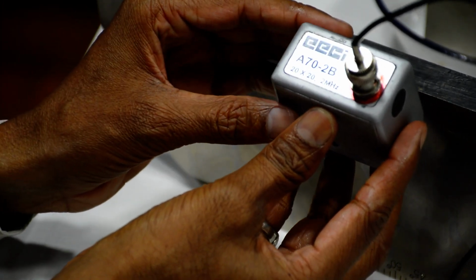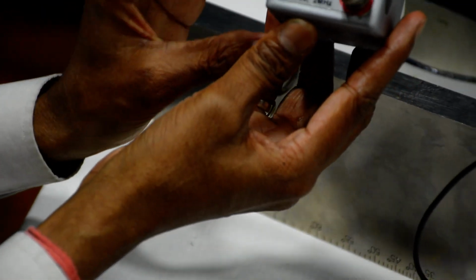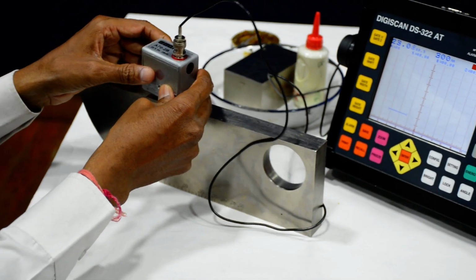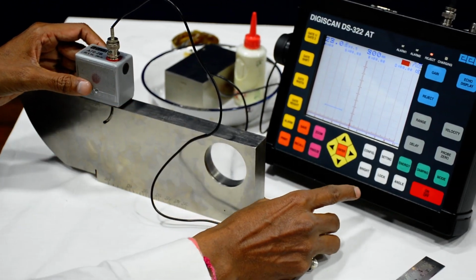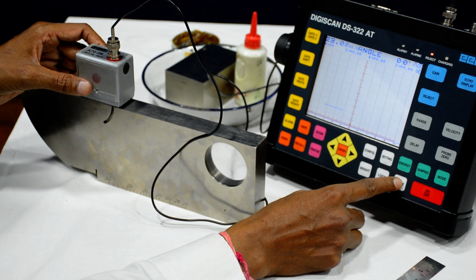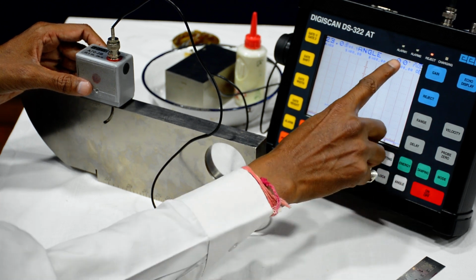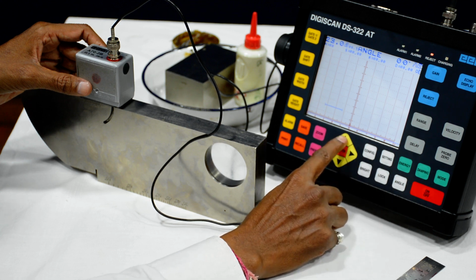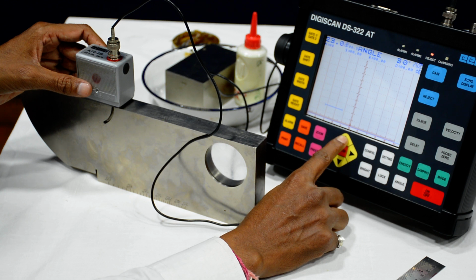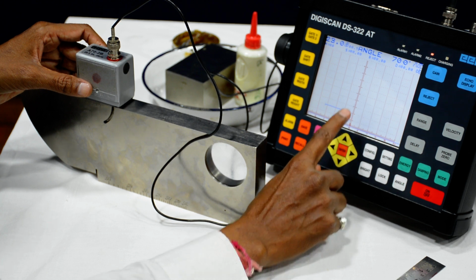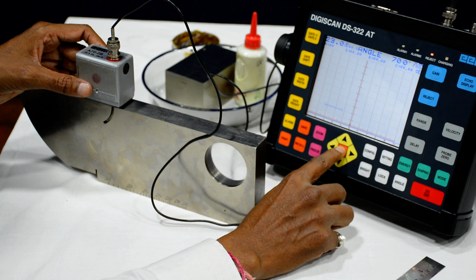Okay, now we will do the calibration for the 70 degree. This is the 70 degree single crystal probe. So first we have to change the value for this 70 degree probe. First we will check the angle. Here angle is 0 degree. So first we have to make this angle 70. So we will come to this button and we will make this angle 70 degree. Okay, now this angle become 70. So we will enter this button.